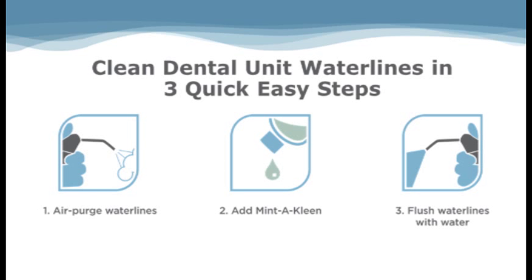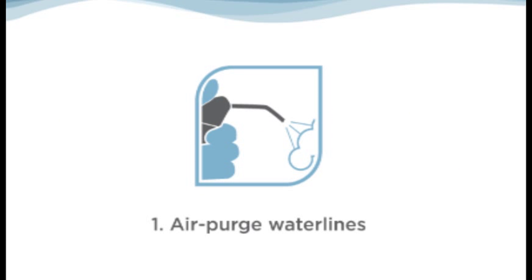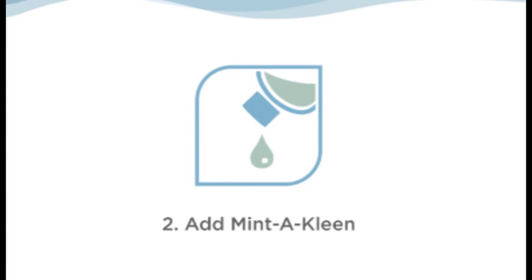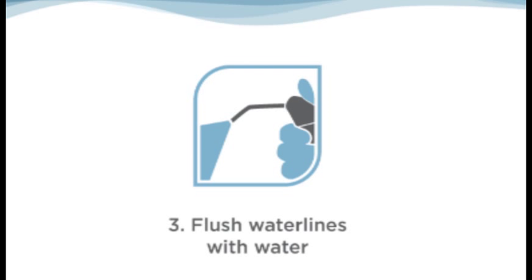To recap, it's three easy steps. Step 1, air purge the waterlines. Step 2, add Mint-A-Kleen. And step 3, flush the waterlines with water.